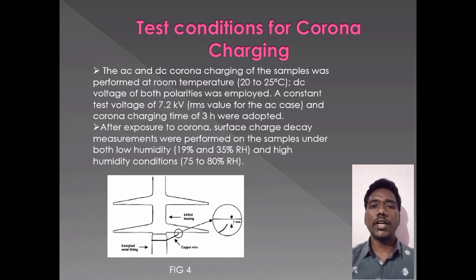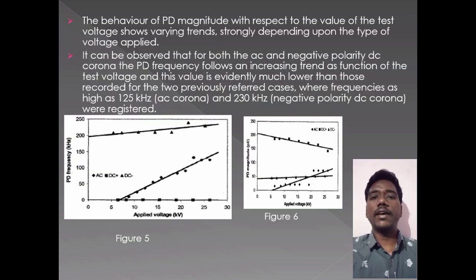High voltage was applied and increased at a steady rate until the first partial discharges were visually registered in an oscilloscope. This voltage was recorded as corona inception voltage. The applied voltage was then further increased several times above the corona inception voltage. In figure 5, the behavior of PD magnitude with respect to the value of test voltage shows varying trends, strongly depending on the type of voltage applied.